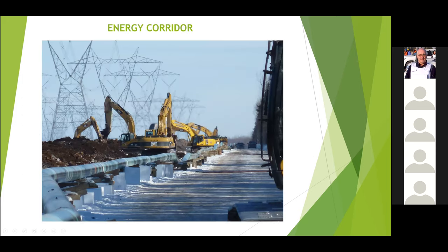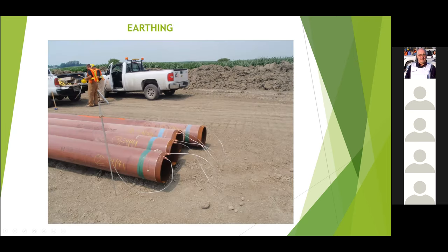Here's an example of one site we were on. You can see all of the power lines — in fact there are three, you can only see two here. They were all very high voltage, and people were getting tremendous electric shocks of 300 or 400 volts. So we had to put some mitigation in and carefully designed the system for them. They came back and said they were still getting electric shocks, saying we hadn't designed it properly. We said the earthing rods were supposed to go in about a metre and a half, but they had only put them in a few centimetres. Once we got them to hammer the rods in properly, that was sufficient to take the voltage off the pipes and they didn't get any more electric shocks.